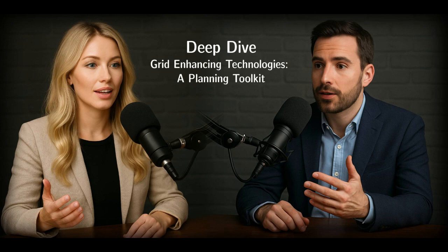Okay, so moving beyond just knowing a line's capacity, the next category is actively controlling power flow. That brings us to flexible AC transmission systems, or FACTS. These are power electronic devices. Exactly. They provide real-time dynamic control of transmission power flows. They can be series devices, shunt devices, or sometimes combined, offering grid-scale optimization, fine-tuning the flows. It sounds like a more surgical approach than just building bigger lines.